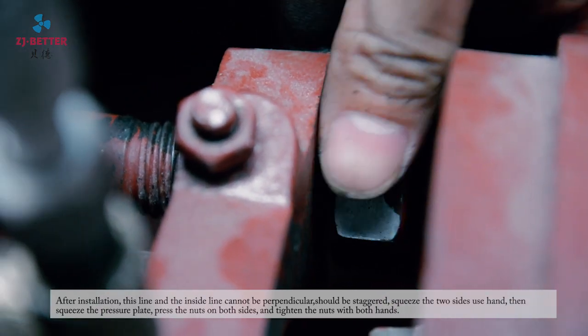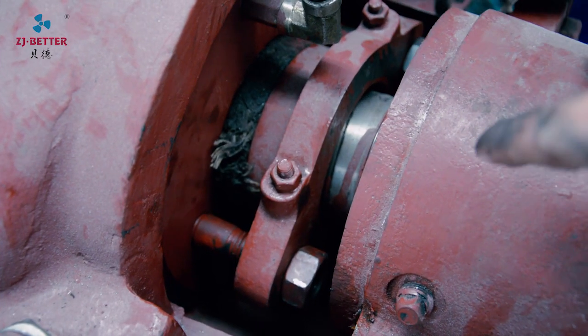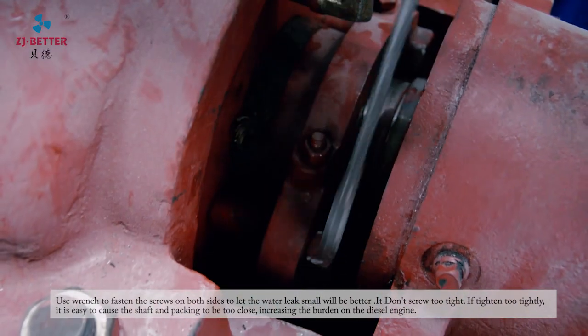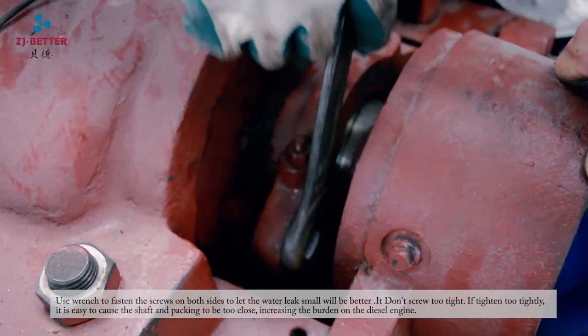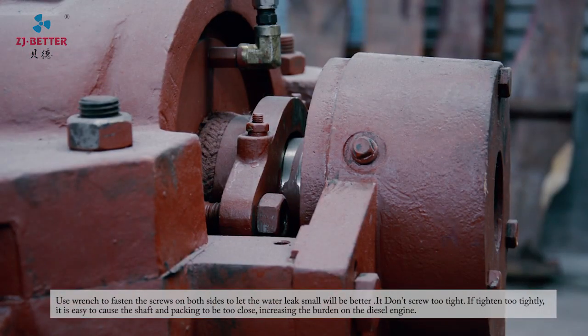Use a wrench to fasten the screws on both sides, allowing a small amount of water to leak — small is better. Don't tighten too much. If tightened too tightly, it is easy to cause the shaft and the packing to be too close, increasing the burden on the diesel engine.